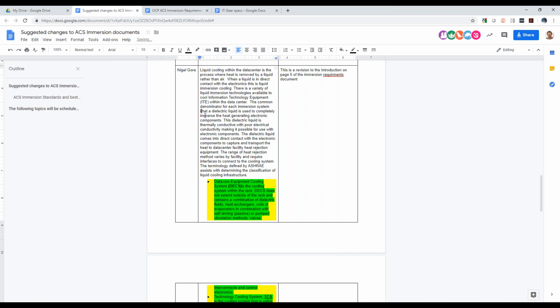Should we put an 'is'? Yes — a dielectric liquid is used to completely immerse the heat generating electronic components. This dielectric liquid is thermally conductive with poor electrical conductivity, making it possible for use with electronic components. A dielectric liquid comes into direct contact with the electronic components to capture and transport the heat to a data center facility heat rejection system — space after 'data center', space before 'center'. The range of heat rejection methods varies by facility and requires interfaces to connect to the cooling system. Terminology defined by ASHRAE assists with determining the classification of liquid cooling infrastructure.